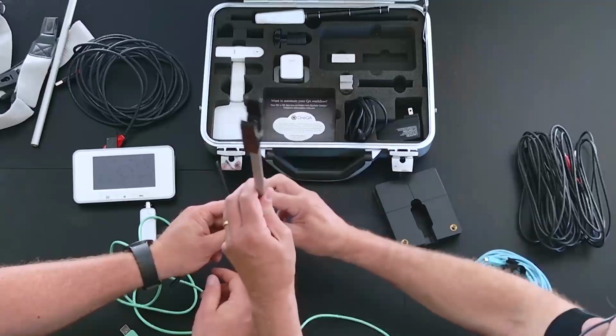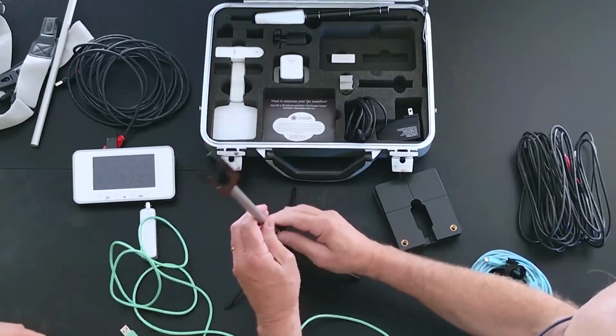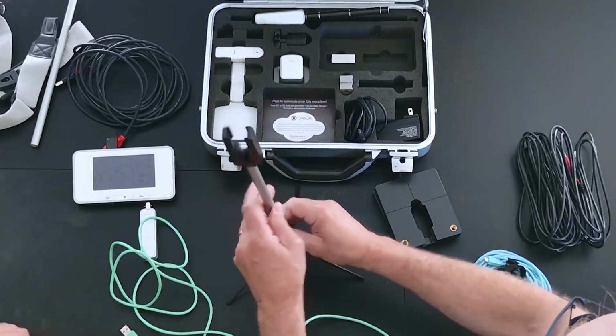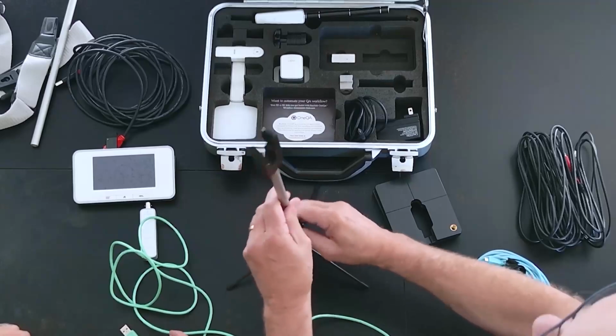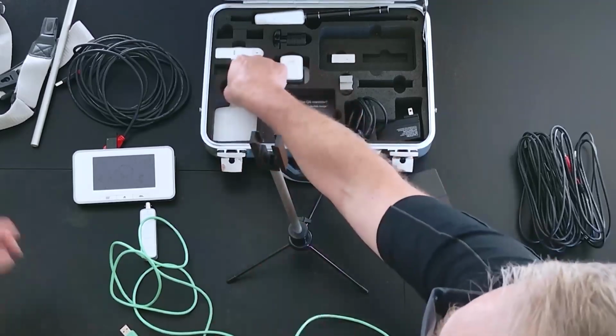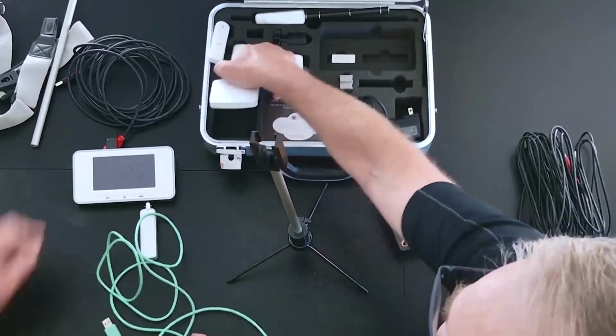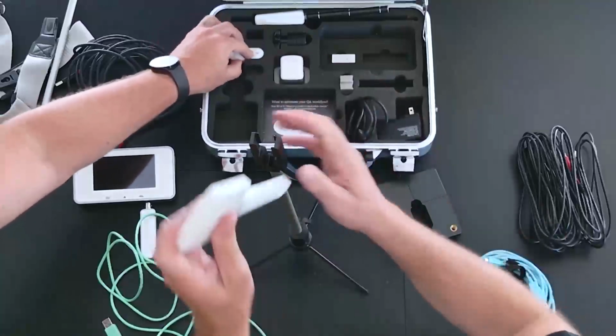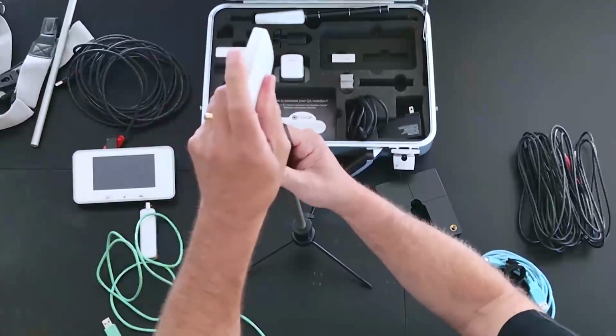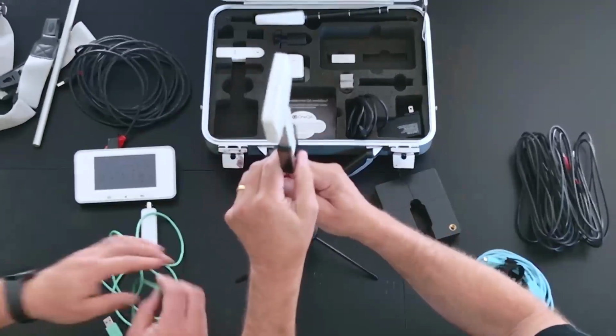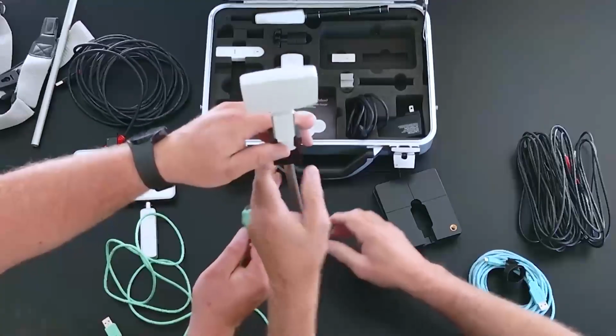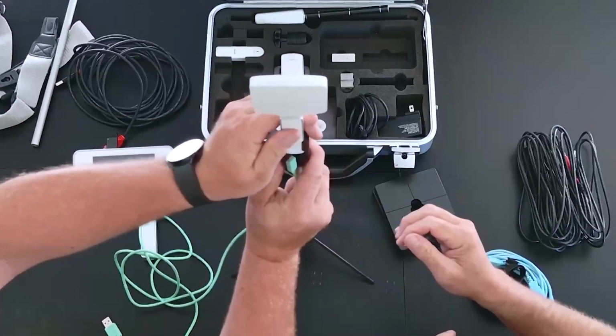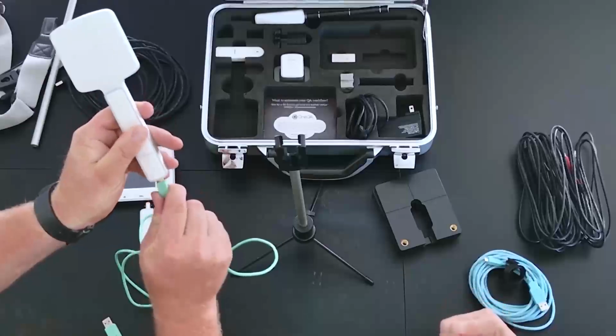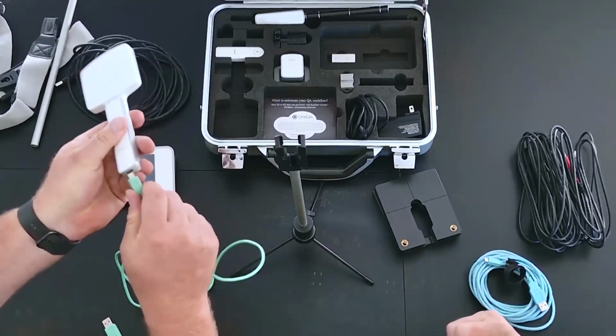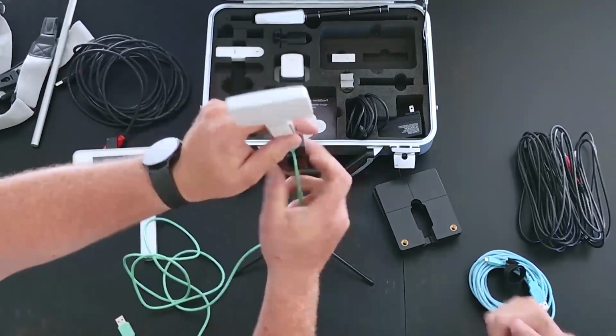Let's say you wanted to measure leakage and you don't want to be in the room as you're measuring leakage. Correct. Tube leakage, for example. What would you do? So I probably use your survey sensor. I'm stealing your thunder. You're having fun. I'm having fun. So you position this as such. That's a little high, but yeah, you can position this. Of course, the cable, you'd run that through. You should always probably connect it before you put it in. You got so excited to steal my thunder. I did. Sorry about that. It's okay.